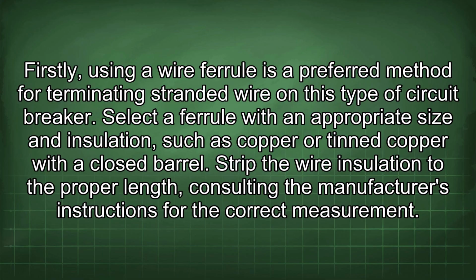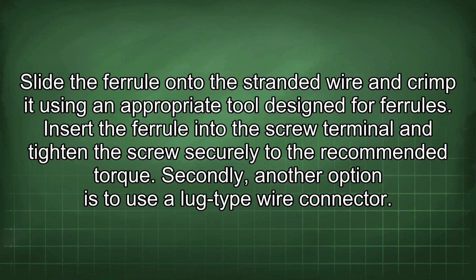of circuit breaker. Select a ferrule with an appropriate size and insulation, such as copper or tinned copper with a closed barrel. Strip the wire insulation to the proper length, consulting the manufacturer's instructions for the correct measurement. Slide the ferrule onto the stranded wire and crimp it using an appropriate tool designed for ferrules. Insert the ferrule into the screw terminal and tighten the screw securely to the recommended torque.